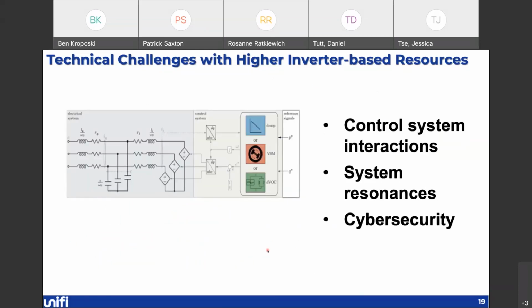And then finally, there's a couple other things just to be aware of, things like control system interactions and system resonances. So depending on how these inverters are actually doing their control algorithms, potentially they could be causing technical interactions with each other that might cause problems on the grid. We really have little understanding in this space because we haven't deployed that many grid forming inverters all running simultaneously. And then another big concern is cybersecurity with this many distributed resources, mostly all having some communication aspects with them.